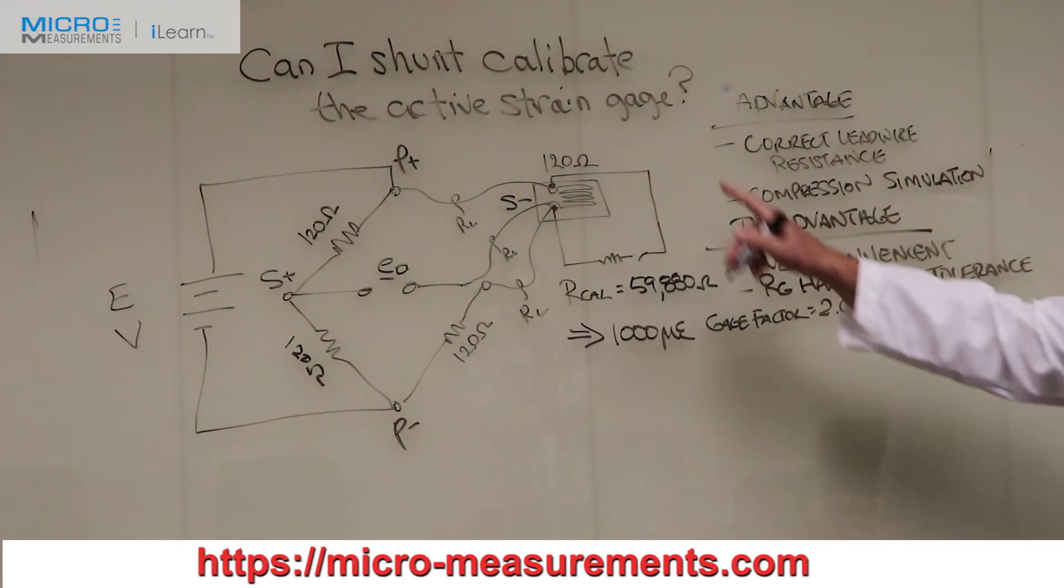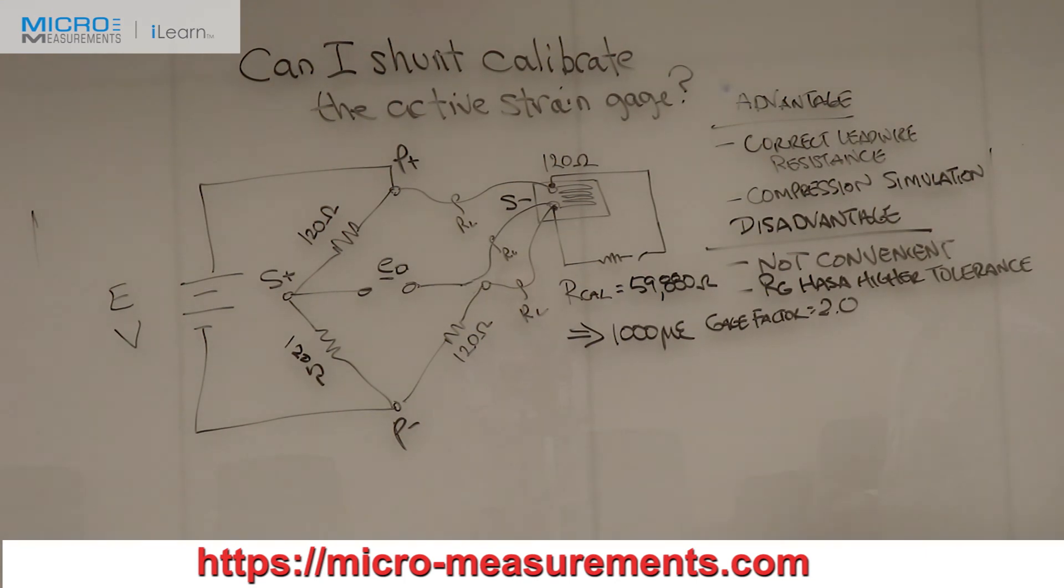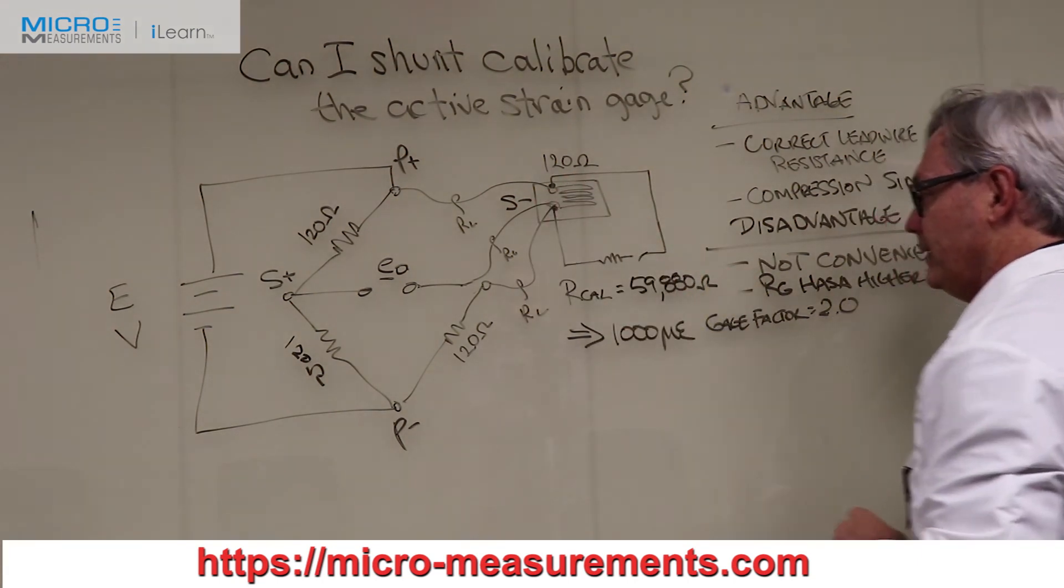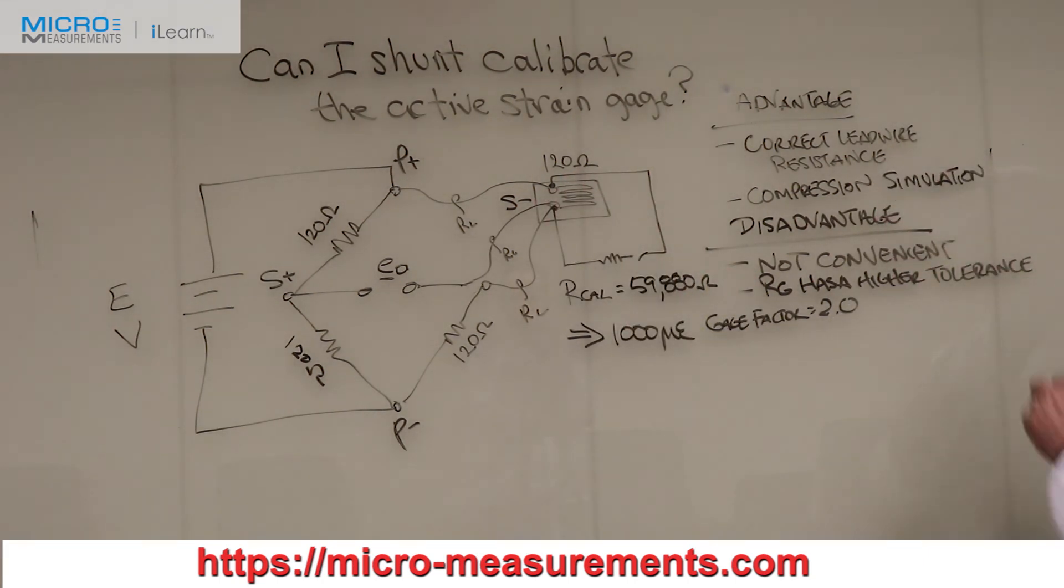So in answer to the question, can I shunt calibrate the active gauge? The answer is yes. It allows you to correct for lead wire resistance. It simulates a compressive strain. And what I would call a disadvantage is that it's not convenient, and typically R sub G has a higher resistance tolerance.